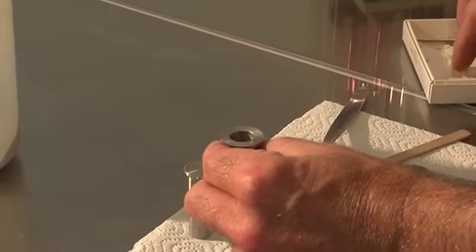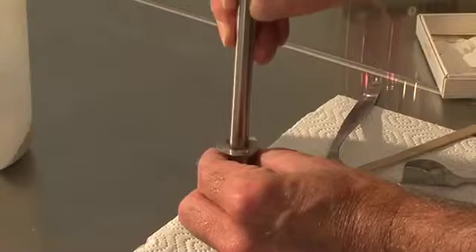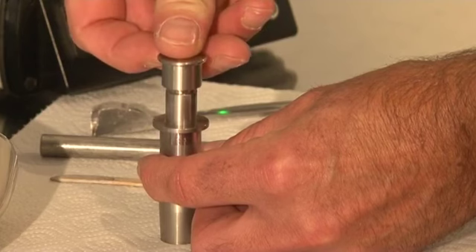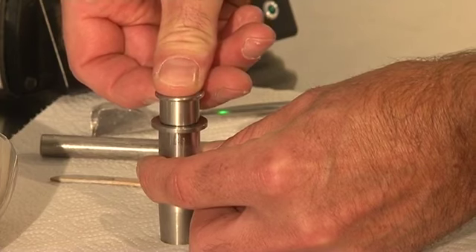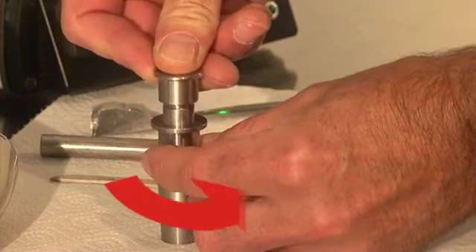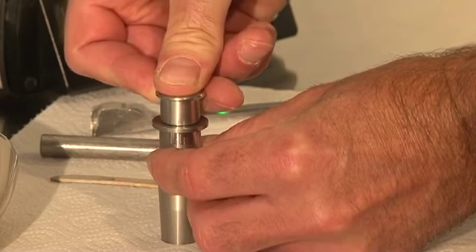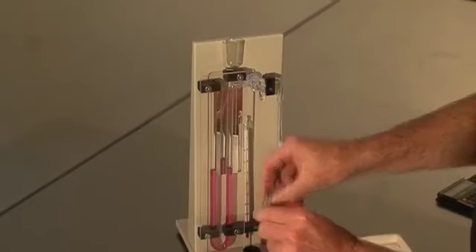The powder bed is levelled by lightly tapping the cell wall. A second filter paper is placed on the levelled surface area. Gently but firmly press the plunger onto the powder bed until the lower face of the cup is in contact with the upper edge of the measuring cell. Then slowly withdraw the plunger approximately 5 mm, rotate it through 90 degrees and press it onto the powder bed again. Slowly withdraw the plunger from the compacted powder bed without disturbing it.